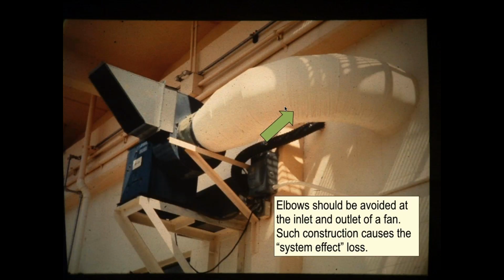We're going to lose that, the turbulence that's going on, noise and heat generated in this fan. If you have an elbow or some other connection like that that's too close to the fan, you're going to introduce what they call system effects, right? And so what you want is you don't want to churn that close to that inlet.